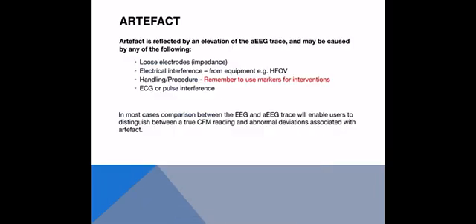Artefacts are false readings that may cause elevations in the CFM trace. They can be caused by impedance issues like loose electrodes, electrical interference from equipment (such as a baby on high-frequency oscillation ventilation), handling or procedures — which is why it's important to use markers on the CFM trace during handling or procedures — and ECG or pulse interference. Comparing the AEEG with the raw EEG helps determine whether abnormal deviations are true or artefactual.